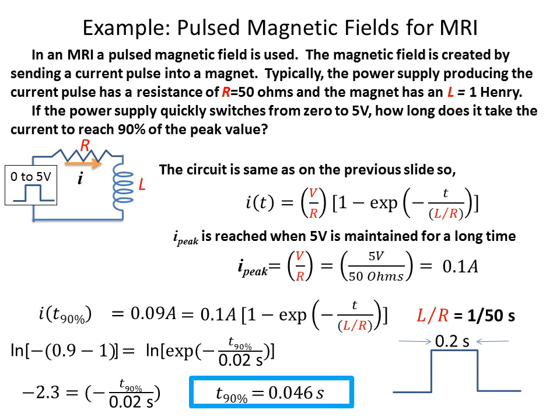What does this mean if we send in a pulse? Consider a pulse that's about two-tenths of a second long. If we apply this zero-to-five-volt pulse to the circuit, the current that comes through will look distorted — instead of having perfectly square edges, it will have a slower rise and a slower fall. So the pulse is distorted by being pushed into this inductor, which may or may not affect how well the MRI system works, but it's important to know.